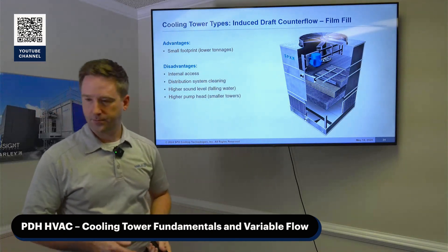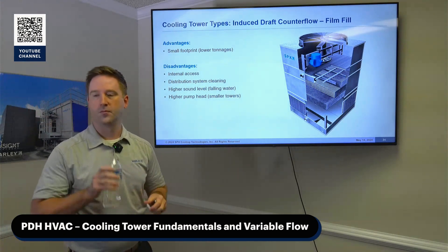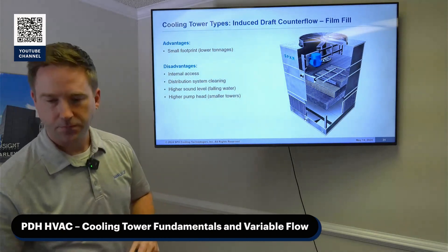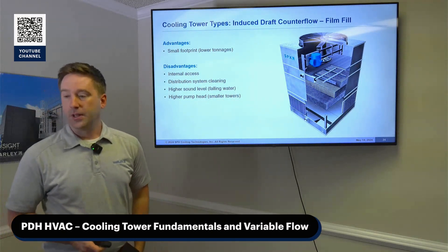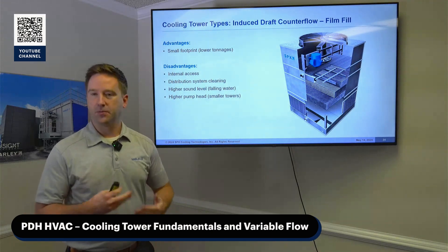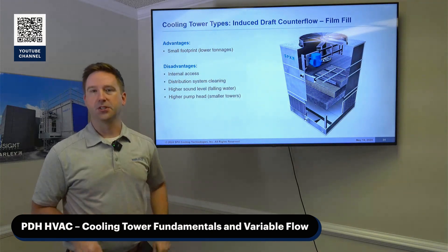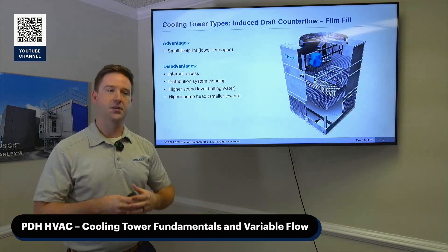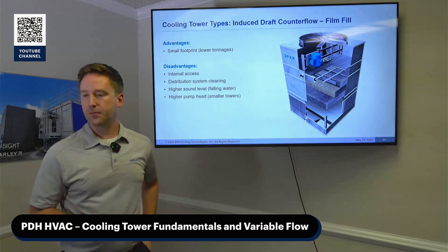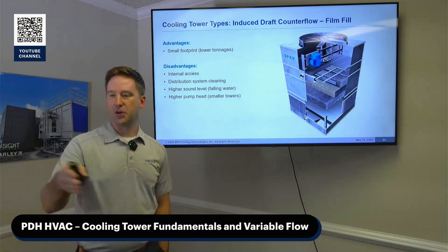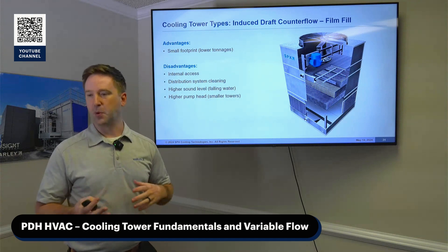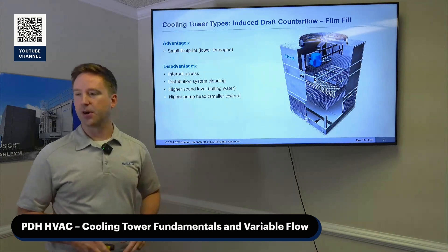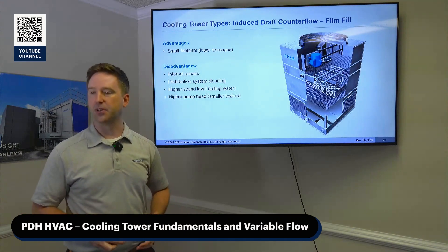There's a question: is the cross-flow the same principle as the counter-flow heat exchanger versus parallel flow? Yes, same principle — it's just the air versus water orientation. The whole principle is to get as much air-to-water interaction to drive evaporation, which is where you get your cooling. They each have their place: from a maintenance standpoint, the cross-flow outshines by far, but if you need something in a tighter spot, the counter-flow fits very well.